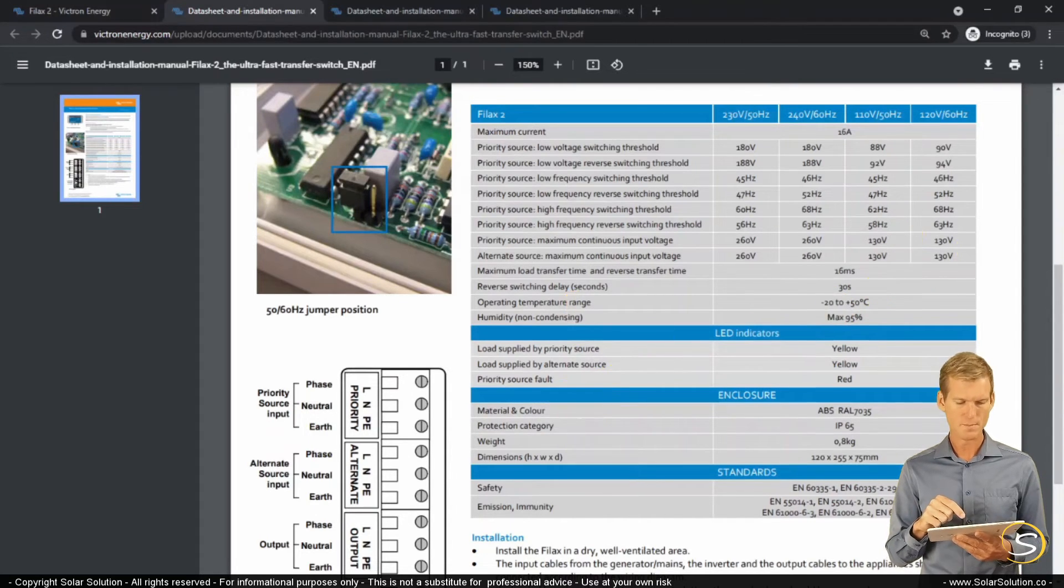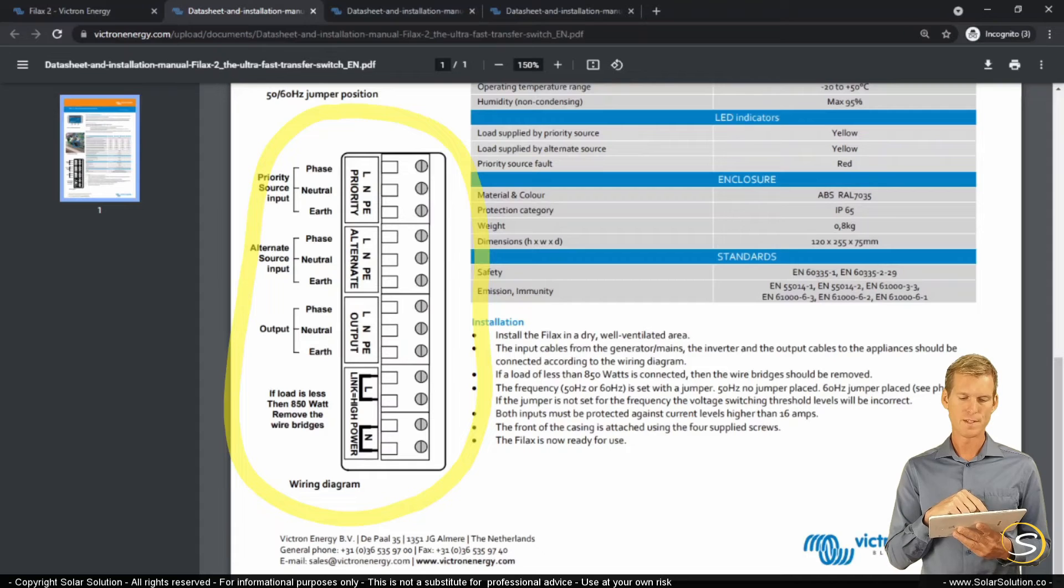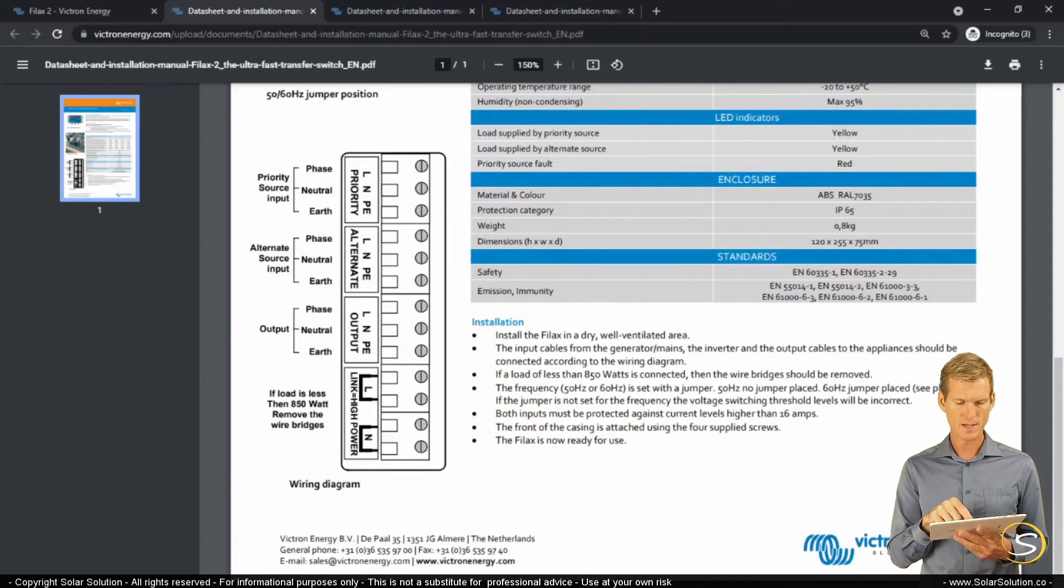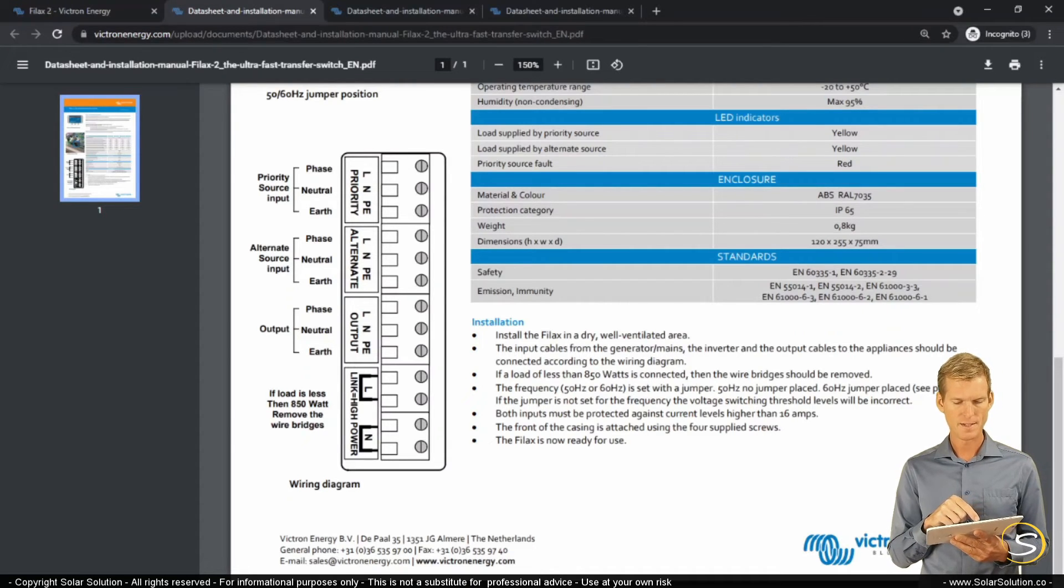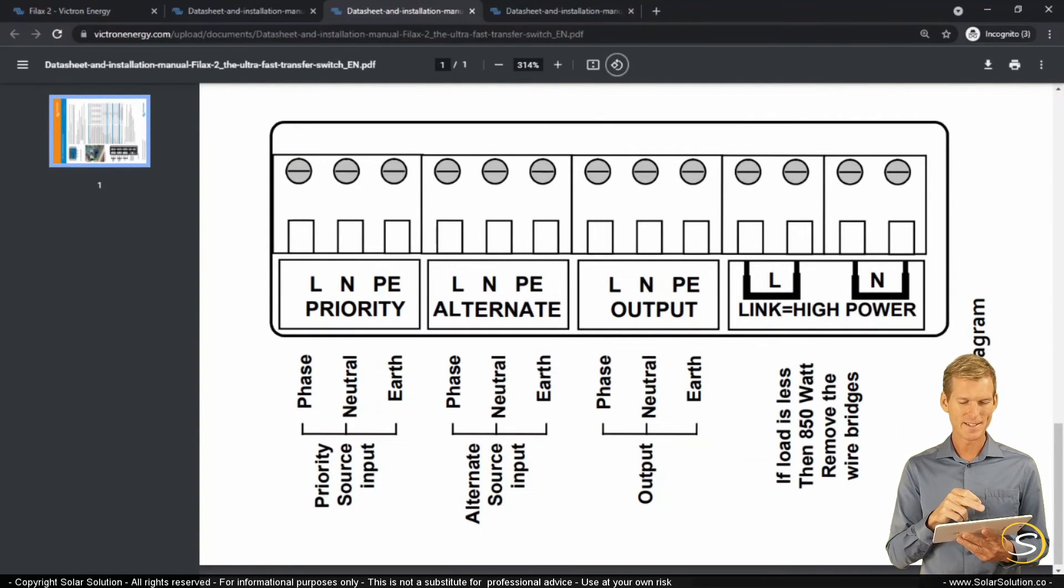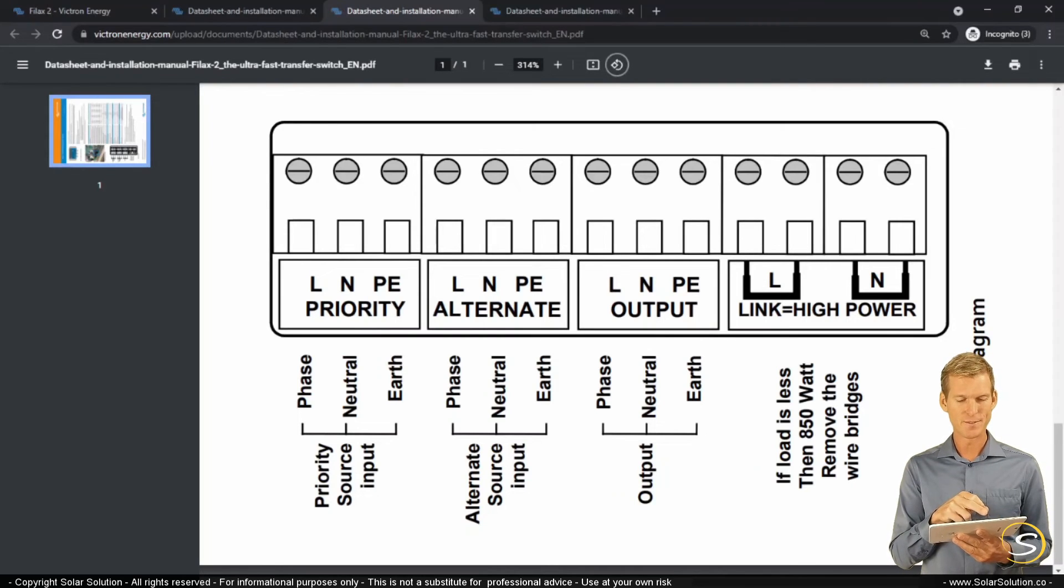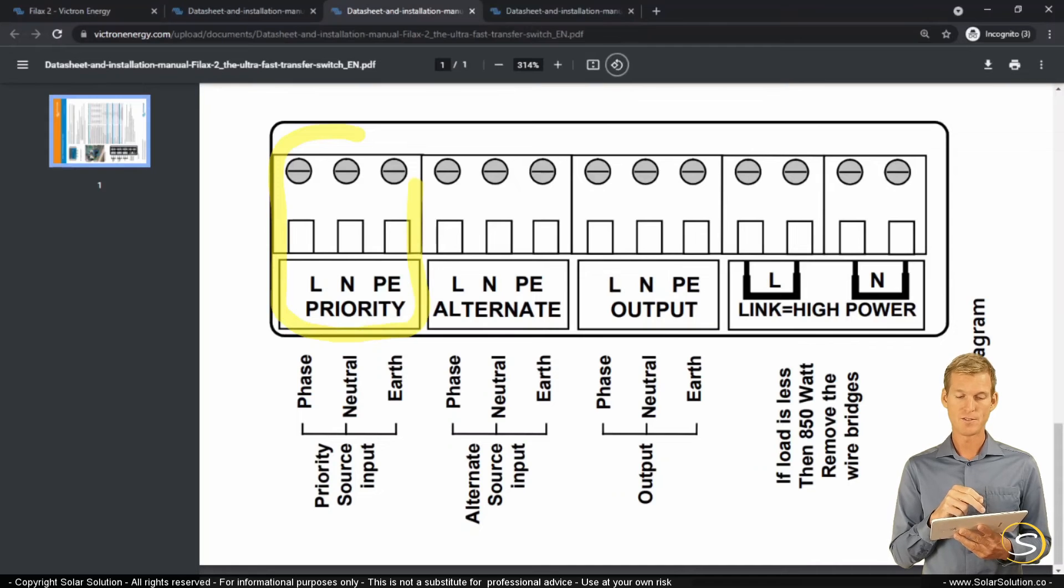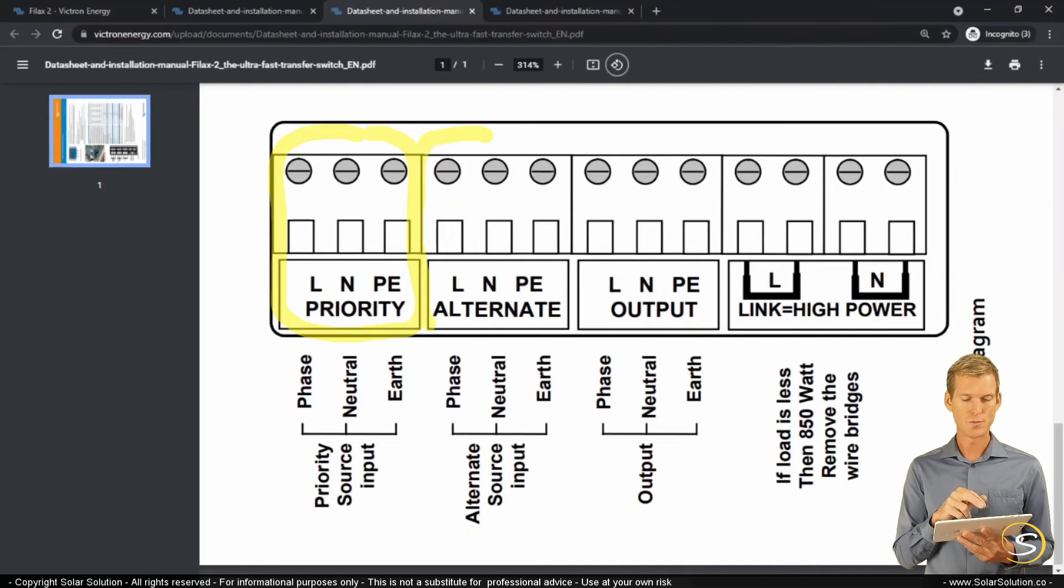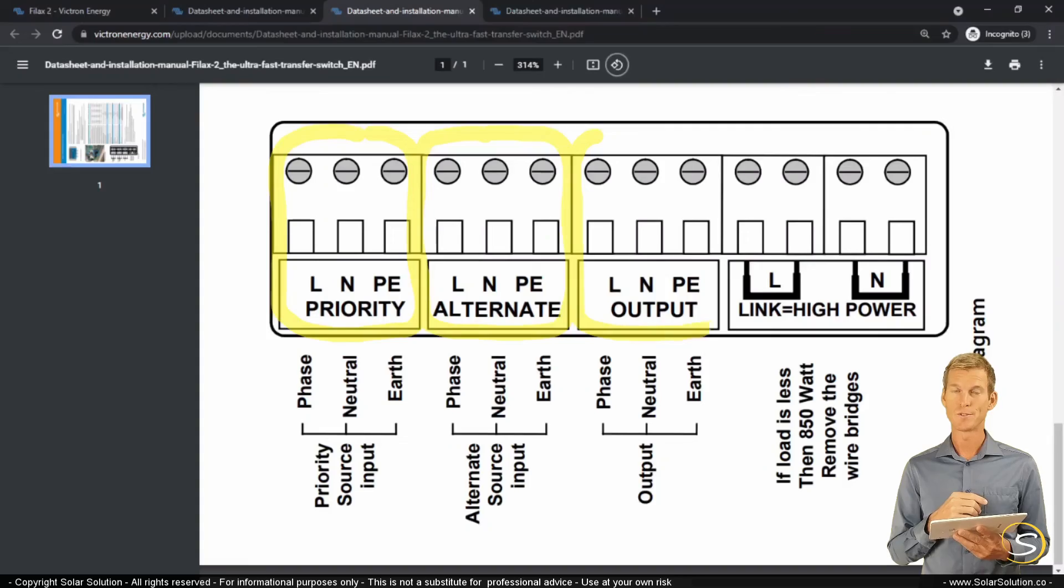Now let's look at the bottom left here. I want to have a look at the connection terminals of this ATS. So let's zoom in a little bit and turn it to the left so that it will be a little bit easier to understand. So here you can see what I just explained in theory, right? So these are the connection terminals of the ATS. And you connect your grid to the first one, to your priority. You could connect your generator to the second one, to your alternate. So those are your two inputs with your live, neutral and your earth. And then you have one output which goes towards your loads.